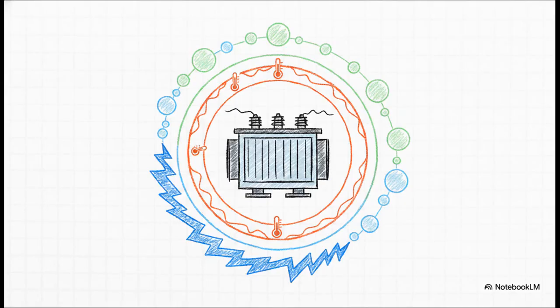But differential protection doesn't fly solo. It's just one part of a layered defense strategy. Think of the differential relay as your incredibly fast reflex to a sudden acute injury, but you still have to monitor the long-term health, right? That's exactly why the system builds in secondary defenses. We're talking thermal tracking and mechanical gas monitoring, which makes sure absolutely nothing slips through the cracks. It's a comprehensive safety net for some seriously expensive hardware.